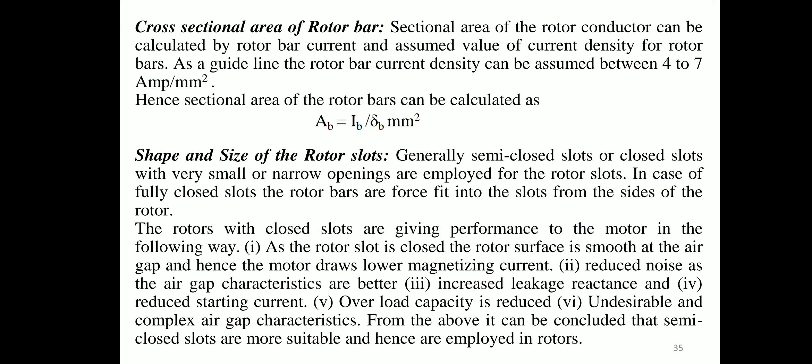The cross-sectional area of rotor conductors is calculated from rotor bar current and assumed current density. The rotor bar current density can be assumed between 4 to 7 A/mm². Hence sectional area of rotor bars: Ab = Ib / δb mm².